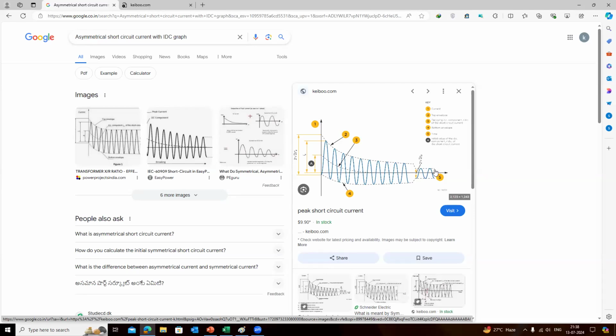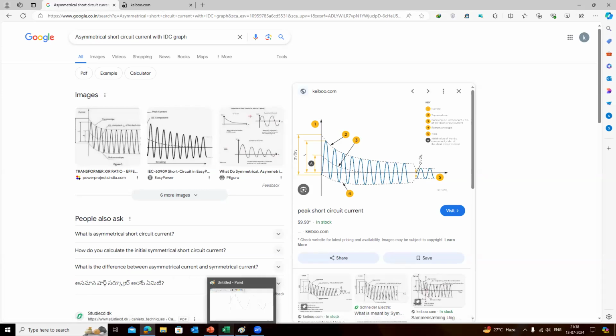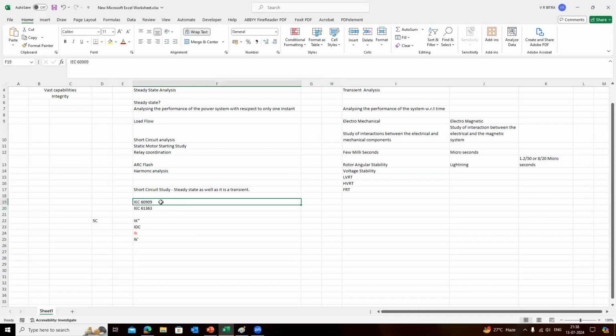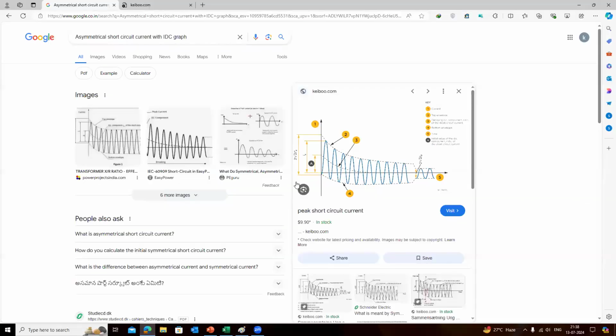So basically 60909 talks about the steady state current, which is a constant irrespective of the instant at which the fault happens. So that's why the short circuit study we perform using ETAP with 60909 is the steady state short circuit. Whereas if you perform the short circuit analysis for 61363, then that is the transient short circuit, because in this we are going to calculate IK double dash, IK dash, IDC, everything in IEC 61363. Okay. Is this clear? Yes, sir.